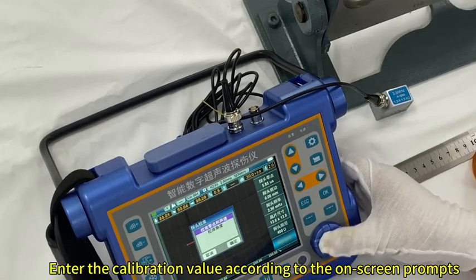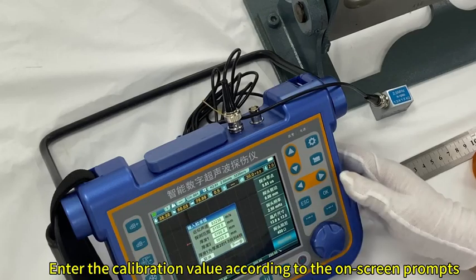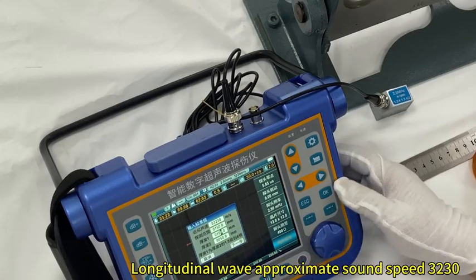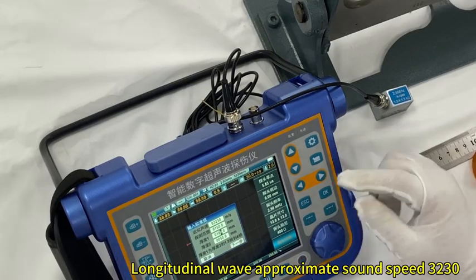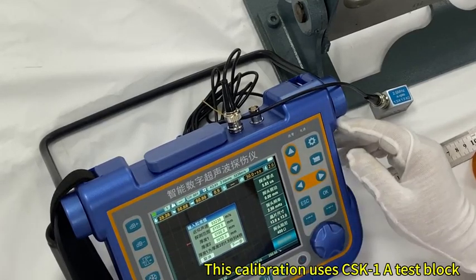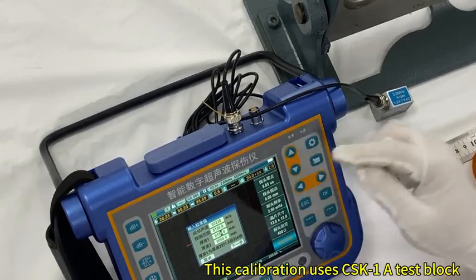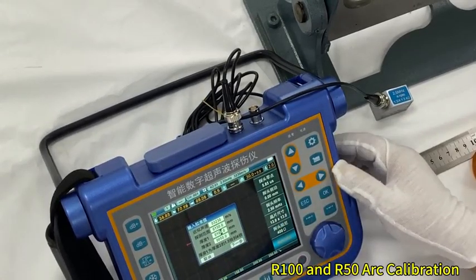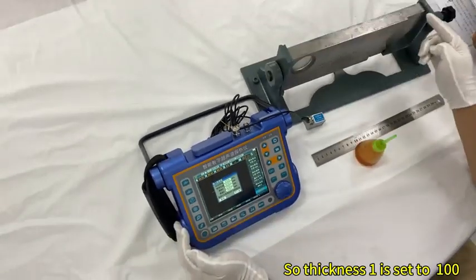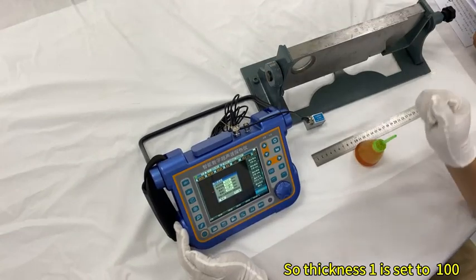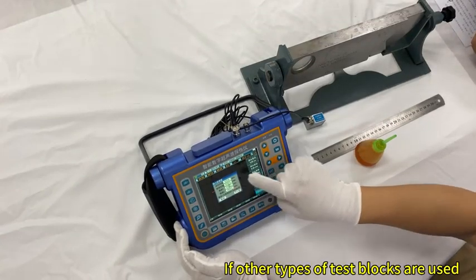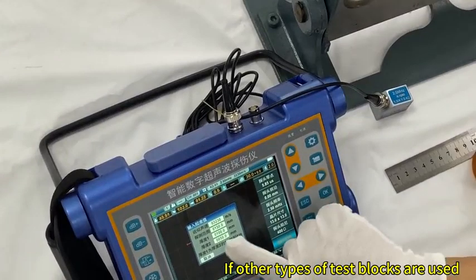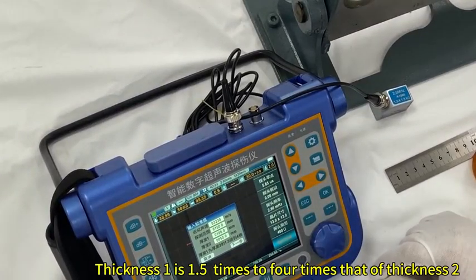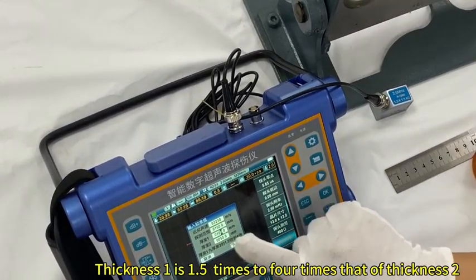Enter the calibration value according to the on-screen prompts. Longitudinal wave approximate sound speed, 3230. This calibration uses the CSK-1A test block, R100 and R50 arc calibration. So thickness 1 is set to 100, thickness 2 is set to 50. If other types of test blocks are used, note that thickness 1 should be 1.5 times to 4 times that of thickness 2.